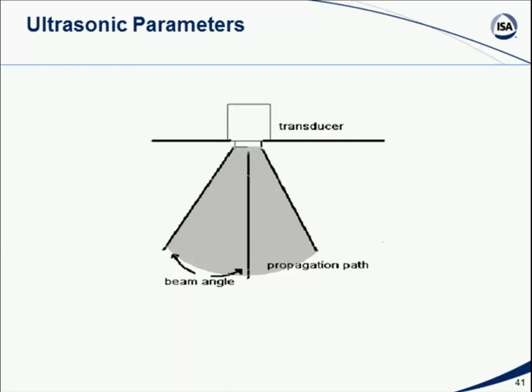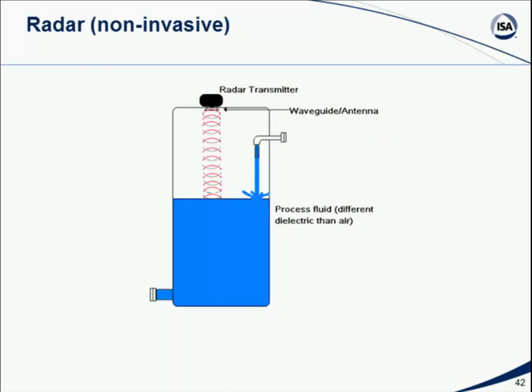Now, ultrasonics, as I said, are affected by temperature. They can be affected also by particulates and vapor pressure and other things. So they're not right for everything, but they are commonly used. But a variation on this same kind of concept of measuring distance down from the top of the tank by timing something is the use of radar. In fact, radar gauge technology was invented years ago and has been used on things like tank ships, large ocean-going tankers, for years to make level measurements. But the costs and technologies have evolved significantly now to where it's very reasonable to consider using radar technology in a lot of other applications.